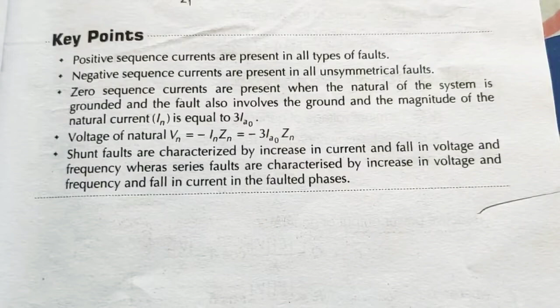Shunt faults are characterized by increase in current and fall in voltage and frequency. Whereas series faults are characterized by increase in voltage and frequency and fall in current. What happens in series faults is that voltage increases, frequency increases, then there is a fall in current in the faulted phase.